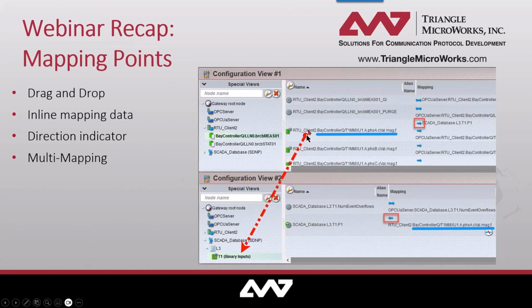For example, you can go to this RTU client for 61850. You can go to the point you're interested in, such as this MMXU, our measurement values. Just grab and drag and drop it where you'd like it to go. Once you do that, you'll see the value is now mapped within your SCADA database being presented up to your control center.